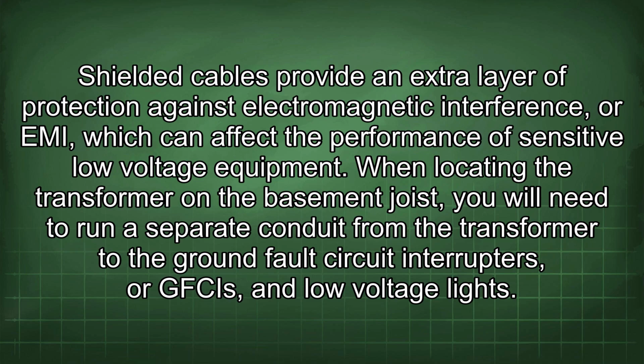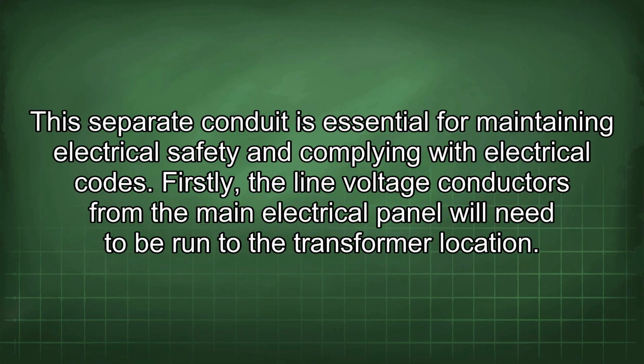When locating the transformer on the basement joist, you will need to run a separate conduit from the transformer to the ground fault circuit interrupters, or GFCIs, and low voltage lights. This separate conduit is essential for maintaining electrical safety and complying with electrical codes.